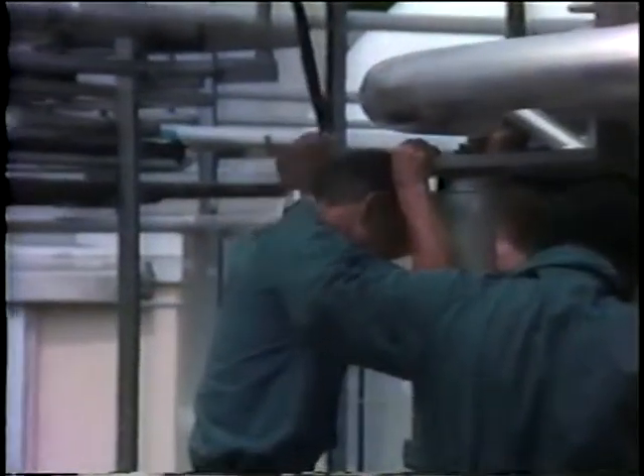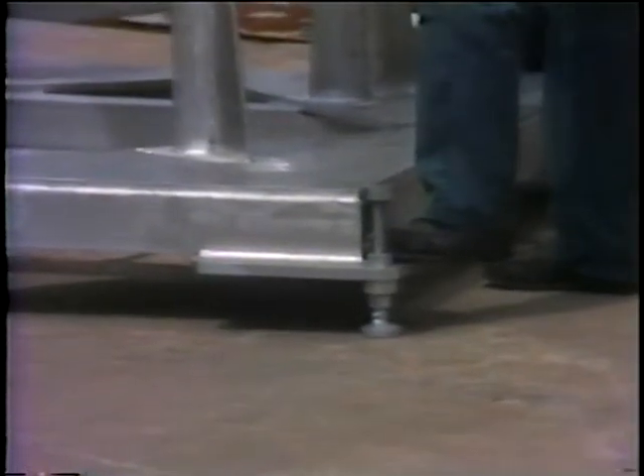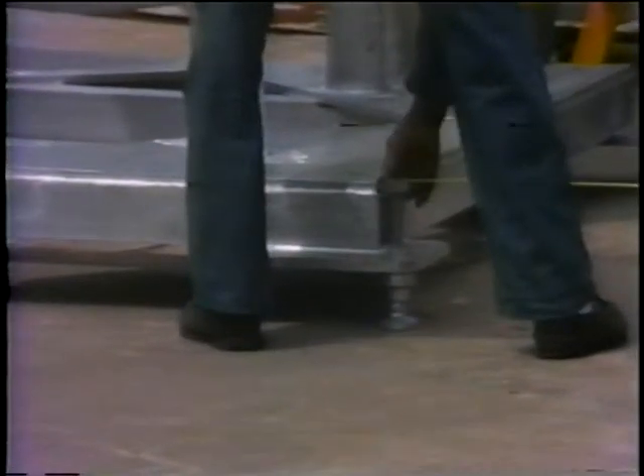Although in an actual system, three cables would be used in a three-phase system, the tests performed at Brookhaven use two cables in a single-phase circuit. Each cable will carry a rated power of 333 MVA, corresponding to 1,000 MVA on a three-phase basis.